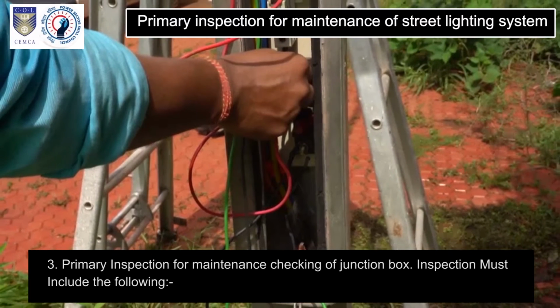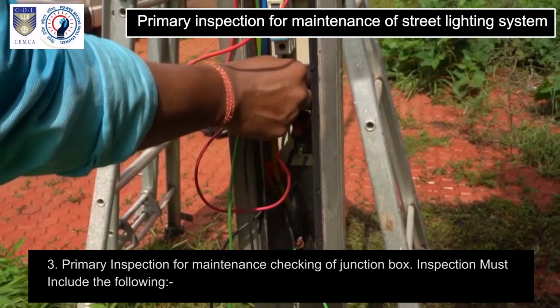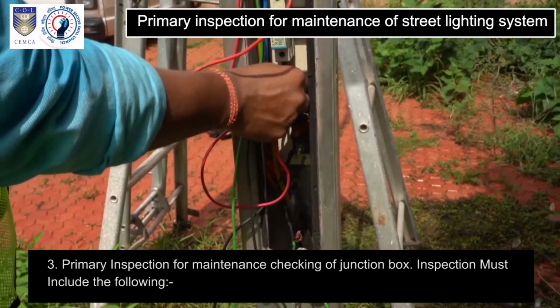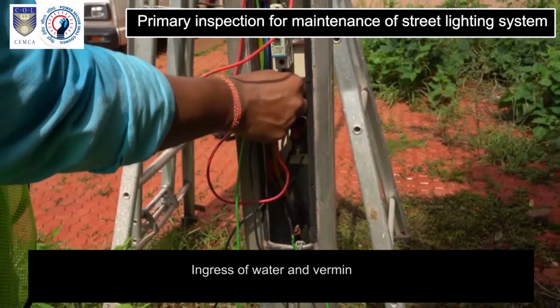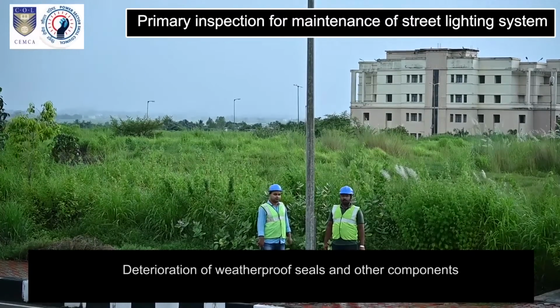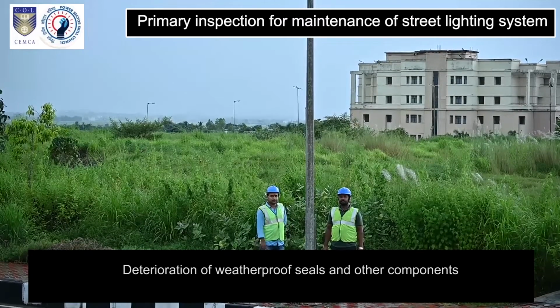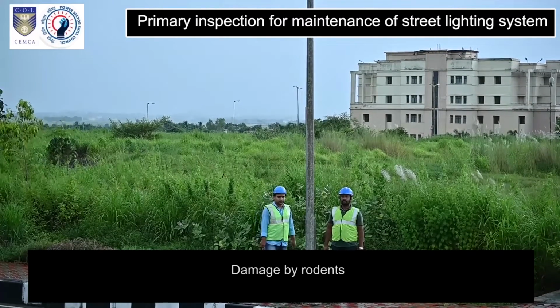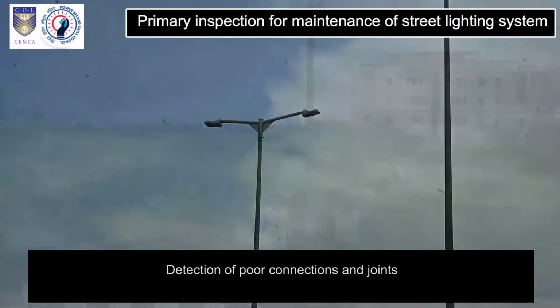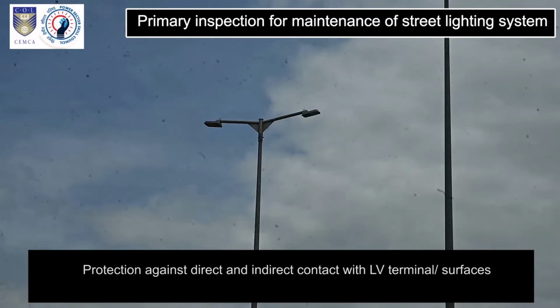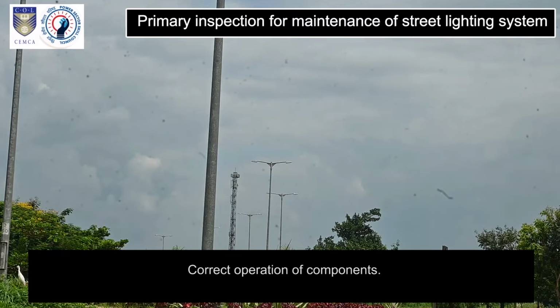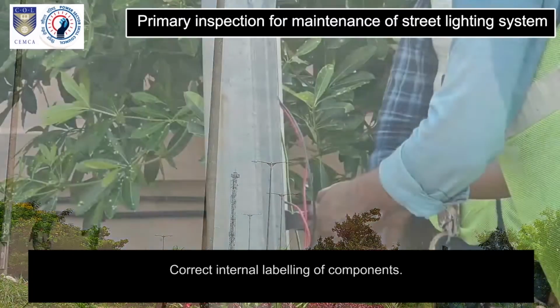3. Primary inspection for maintenance: checking of junction box. Inspection must include the following: ingress of water and vermin, deterioration of weatherproof seals and other components, damage by rodents, detection of poor connections and joints, correct earthing, protection against direct and indirect contact with LV terminals and surfaces, correct operation of components, correct internal labeling of components.